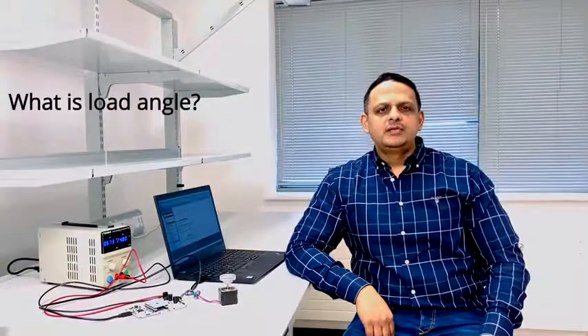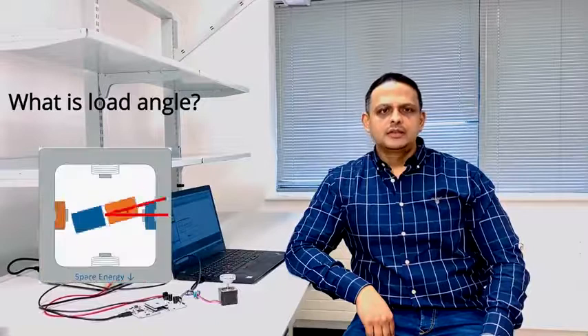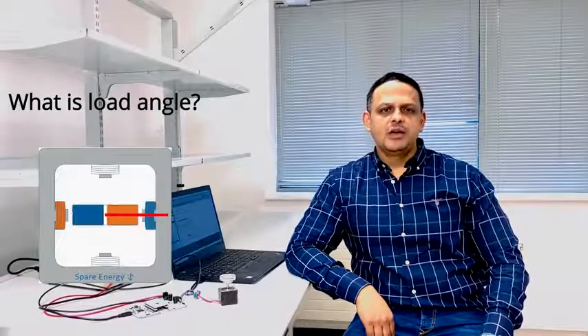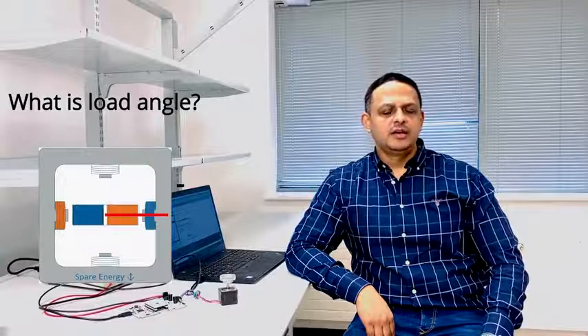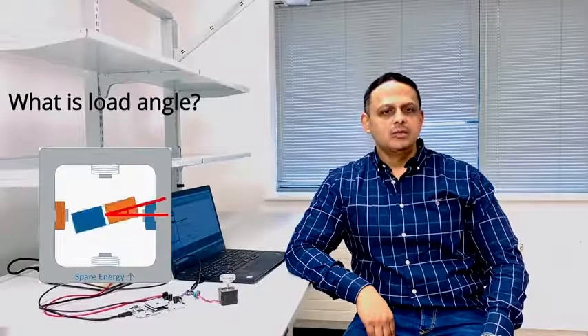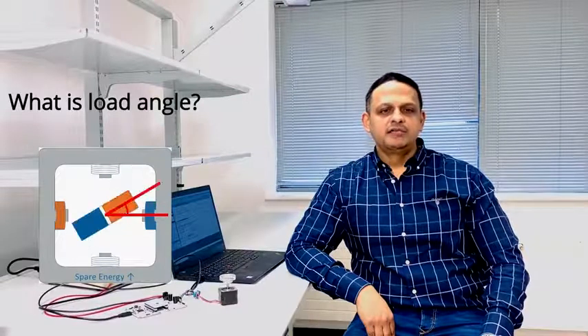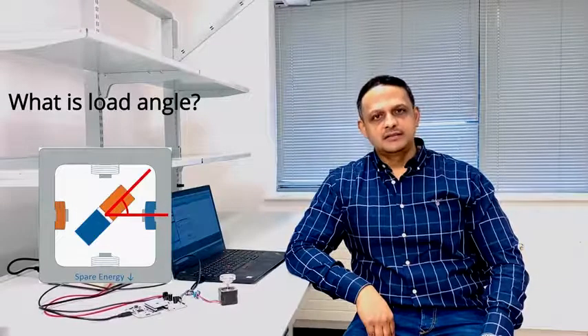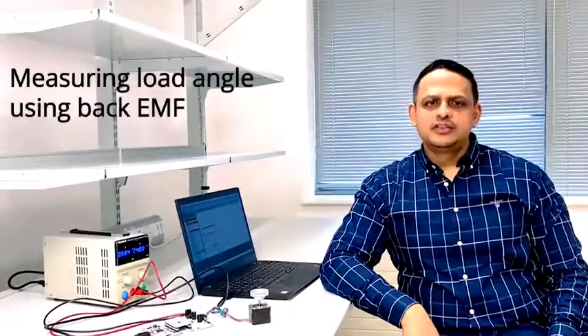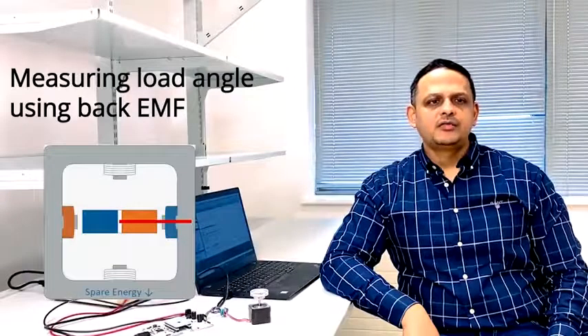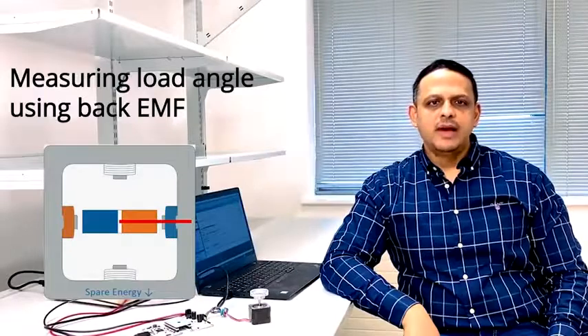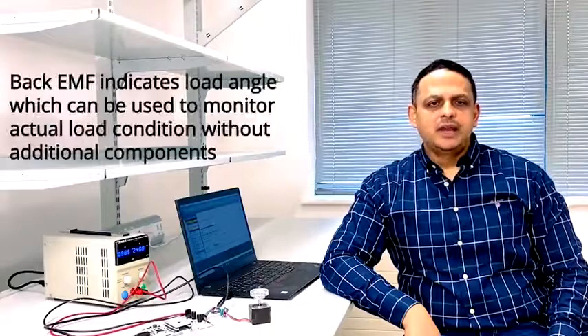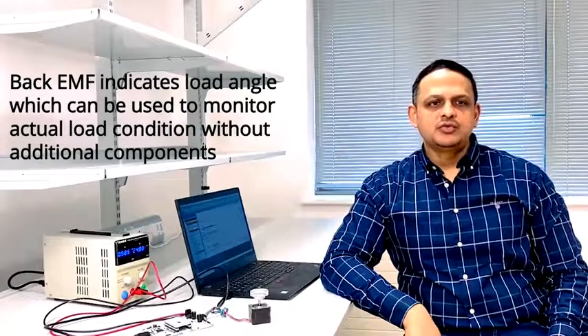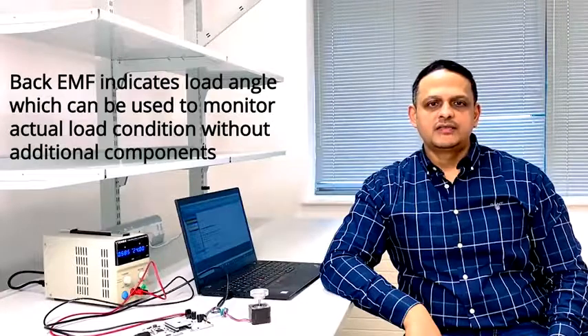The electromagnetic field of the stator pulls or pushes the rotor. This causes a phase shift between the magnetic field of the rotor and the direction of the rotating field of the stator. This phase shift is the load angle, or the angle between the two magnetic field directions of the motor's rotor and the stator. Under normal load conditions, the load angle is low, and part of the energy flowing into the motor also flows back to the power supply, resulting in back-EMF. This back-EMF indicates the mechanical load on the motor, meaning it can be used to monitor the actual load conditions of a drive system without using additional components.